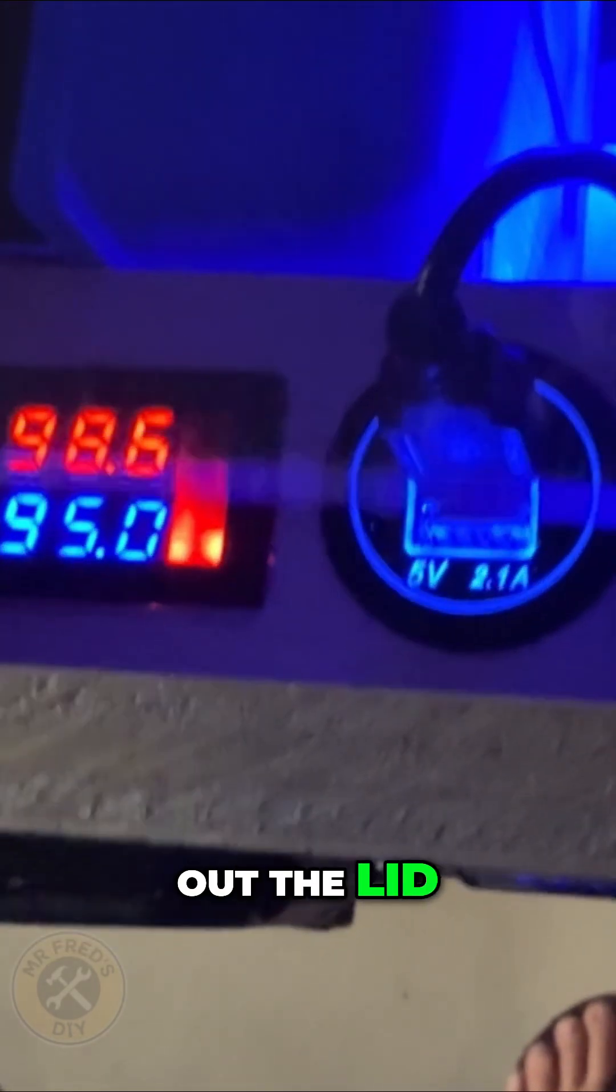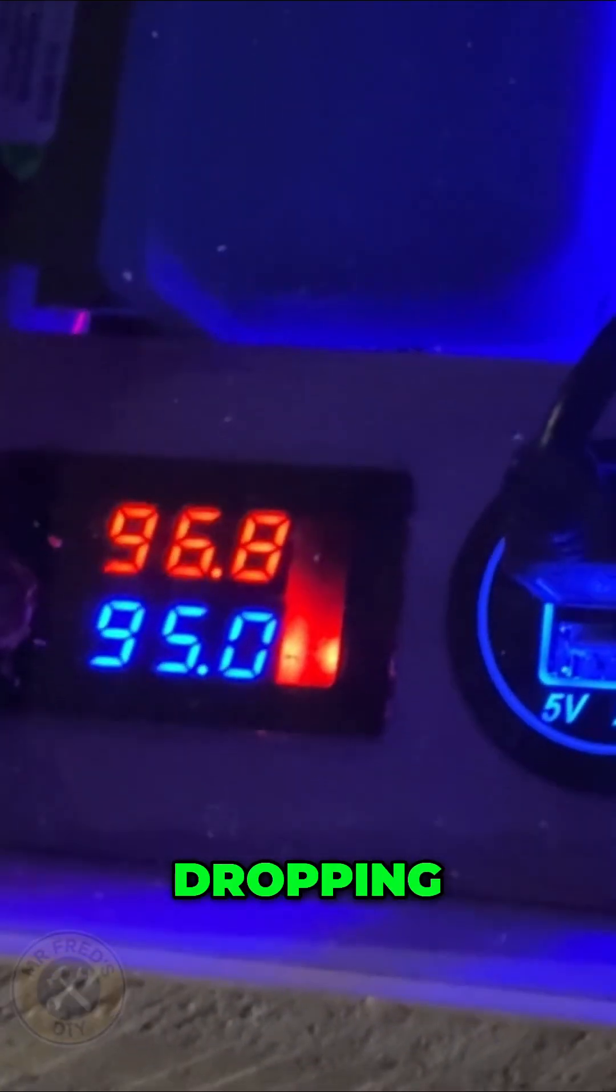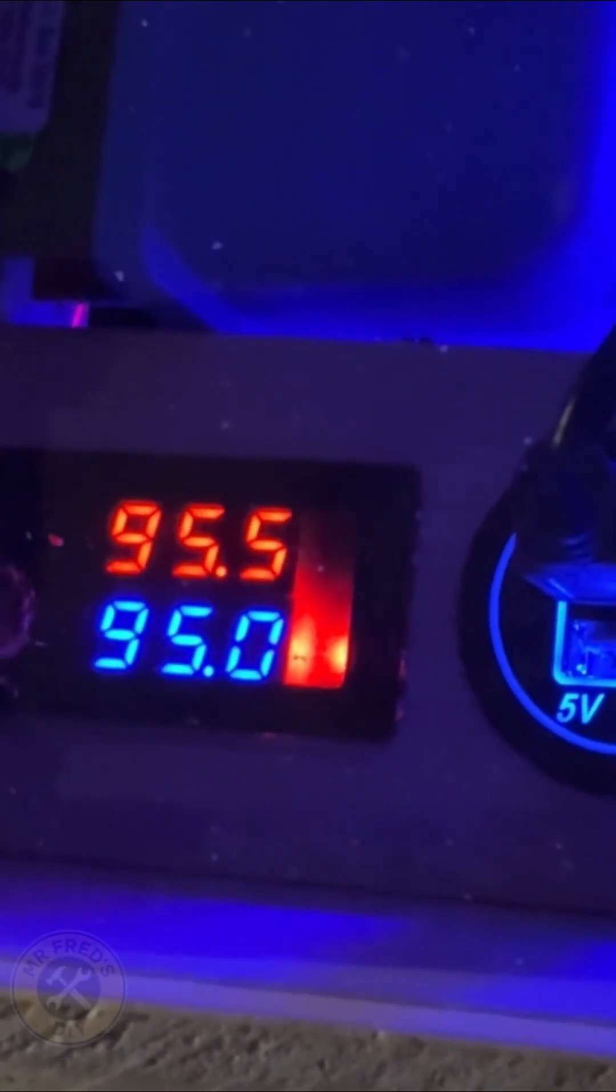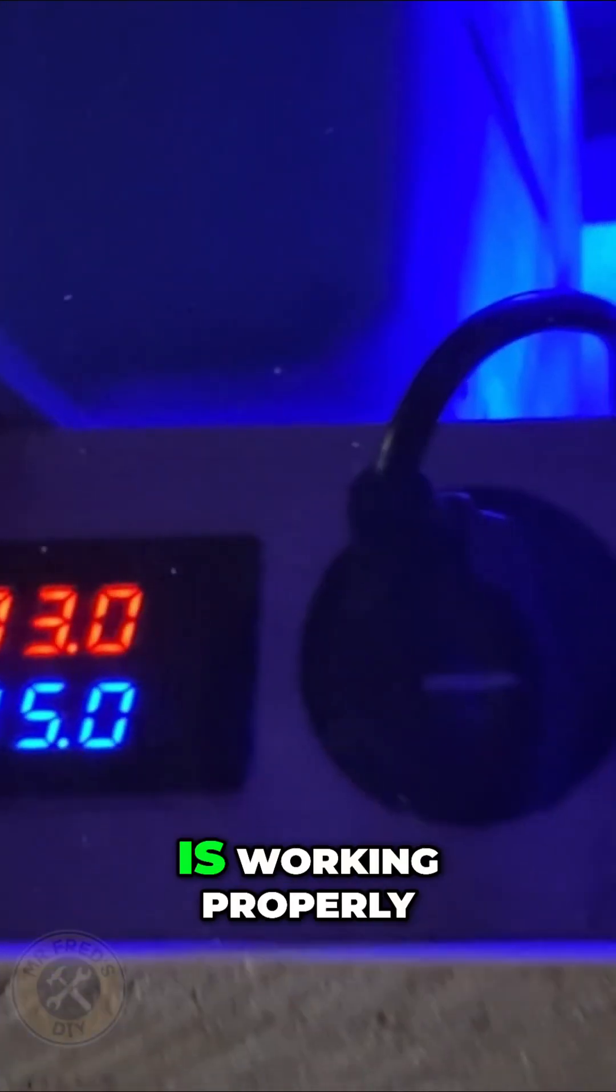Let's watch the temperature drop and when it gets down. Oh yeah, I can feel it coming out of the lid, dropping, dropping and 95 degrees. The light went out. This thing is working properly.